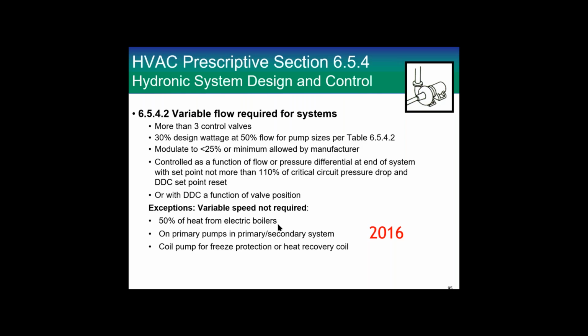Variable speed not required if 50% of the heat is from electric boilers. This is because it's a problem. You don't want to burn up an electric boiler. On primary pumps in primary secondary systems and in the coil pump for freeze protection or heat recovery coil.